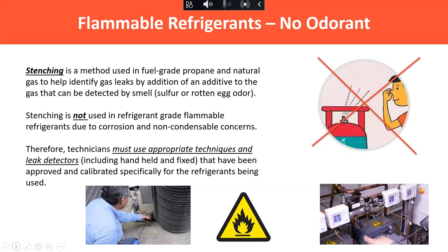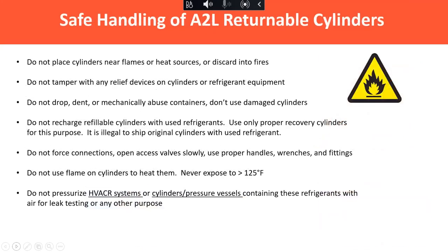In the next chart, dealing with returnable cylinders, I won't read through every one of these—a lot of this falls under best practices: care and respect for our cylinders. In the past, we'd get cylinders back with evidence that people had applied flames or torches to heat them up and build pressure if it was cold out. That's not a best practice and we discourage it—you really don't want to do that with flammable refrigerants. Make sure the mechanical and physical integrity is good: cylinders aren't rusted, valves are in good shape, and we don't force things open. All those good practices around cylinders continue as we move to A2Ls.